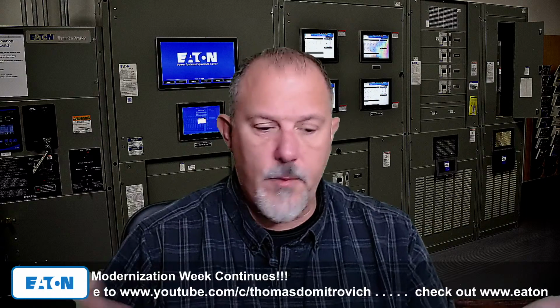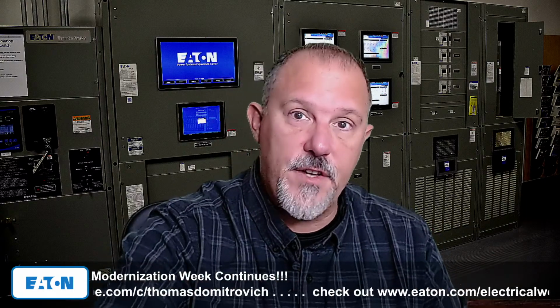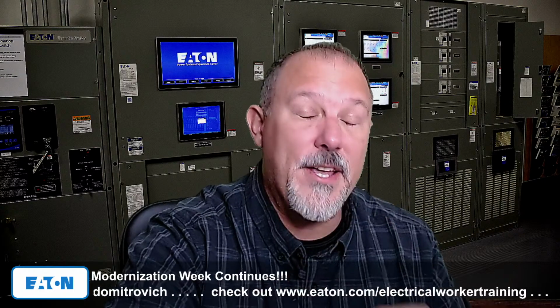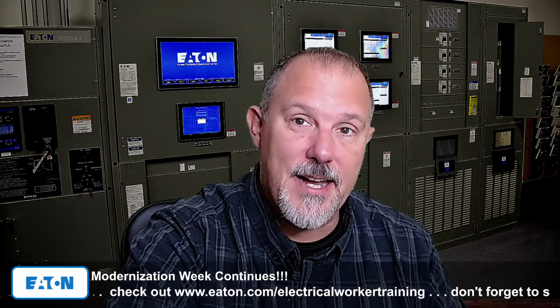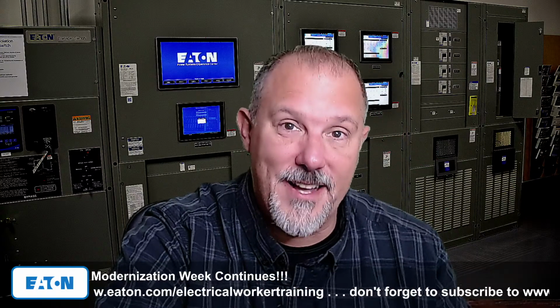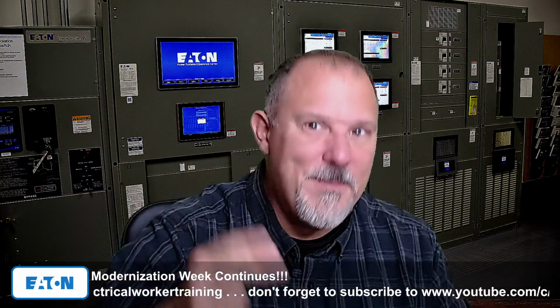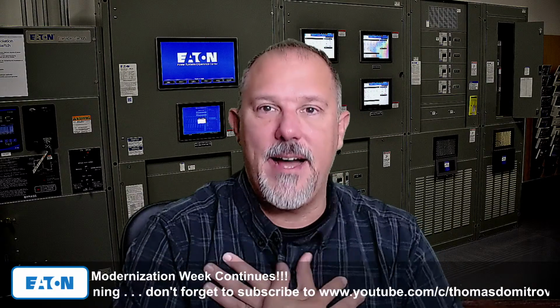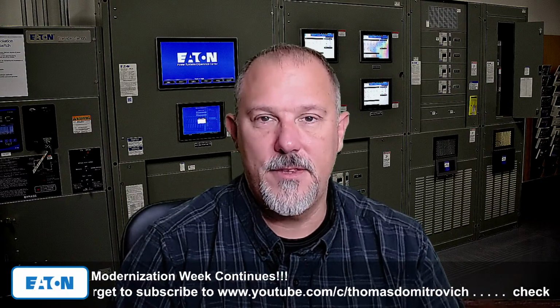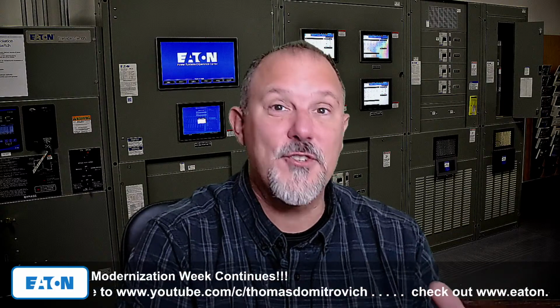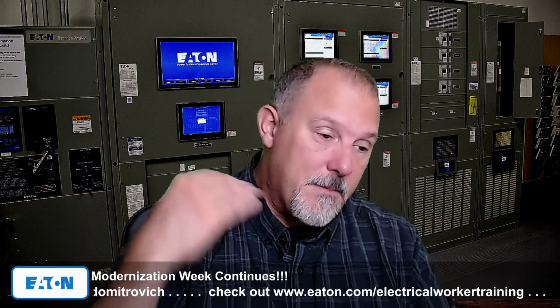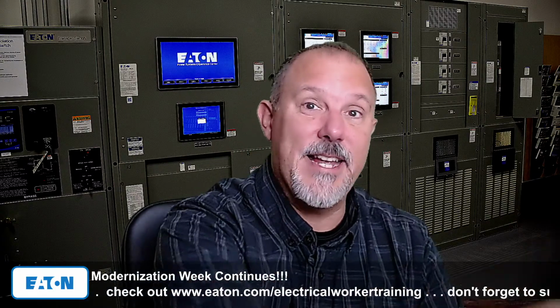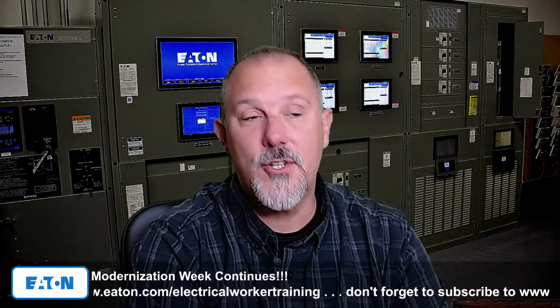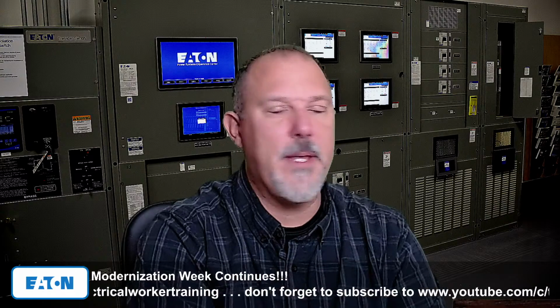But I've even suggested to NEMA and others that we should just create a list. There are high efficiency HVAC units available from very good manufacturers that do not trip a GFCI. There are split units that do not trip a GFCI. There's one or two manufacturers that I am personally aware of that have issues that are causing this uproar. But there are manufacturers who have very good products that are completely compatible. So I said, let's make a list of those, and let's promote the purchase and sale of those products because of this compatibility. There's a reluctance to do that, but I think that would be an awesome list.